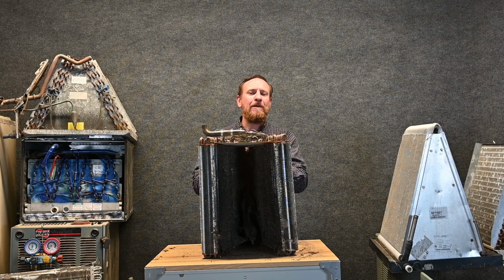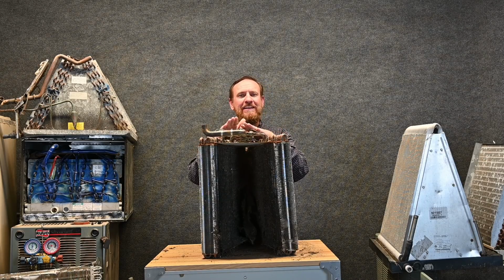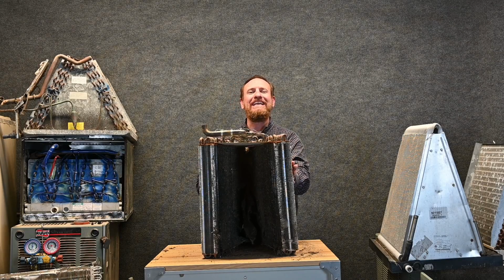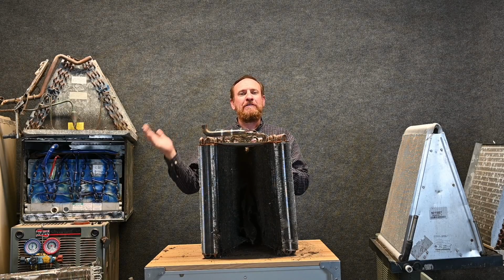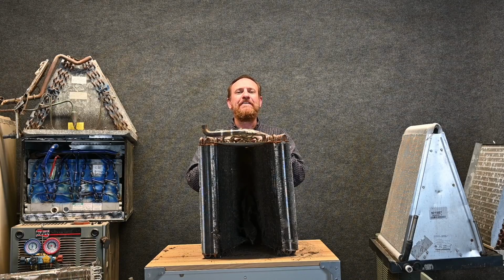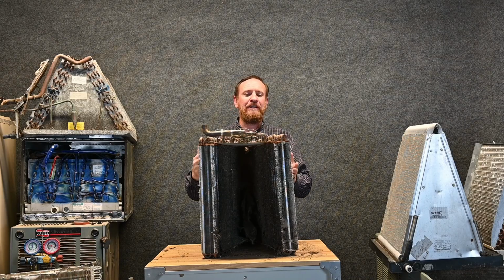It reacts with the copper, but it's pretty safe. But even as safe as that chemical is, you have to severely and very thoroughly rinse multiple times to get all that chemical off, because that chemical will eat away on this evaporator coil. We talked about chemicals in the house eating away the evaporator coil. That chemical will also eat away at this coil if you leave it on there. So we want to make sure we rinse that off very, very thoroughly and that we kill all the bacteria.